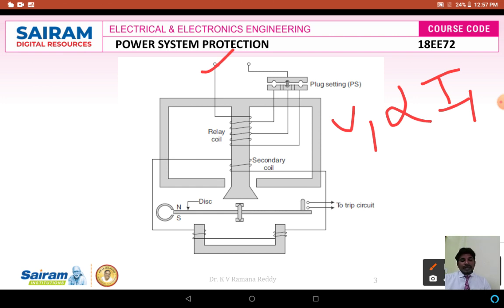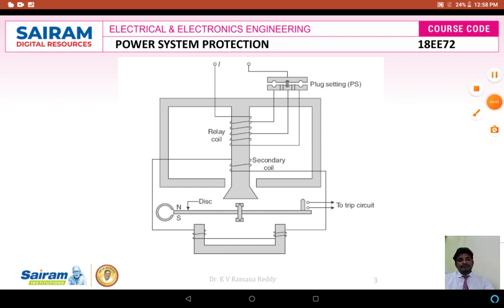When the actuating quantity I1 — the fault current — flows through the relay coil or primary coil, it links to the secondary coil wound on the same center limb of the core of the transformer. Then the secondary voltage V2 is induced in the secondary coil. This secondary voltage V2 causes a current I2 to flow in the secondary winding, which produces a flux Φ2. The interaction of these two fluxes, Φ1 and Φ2, acts on the disc.